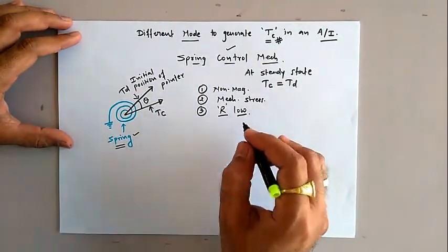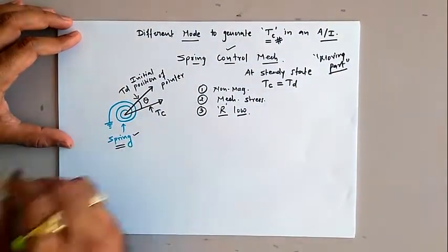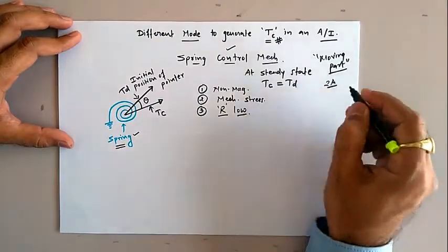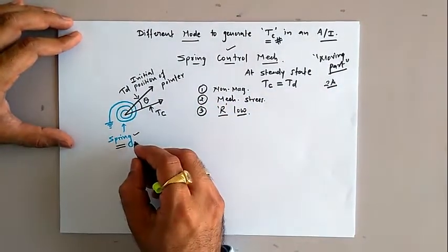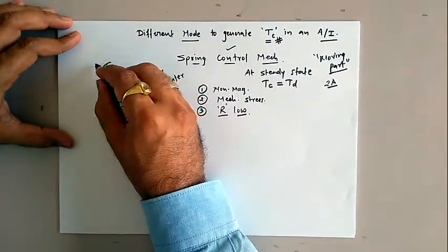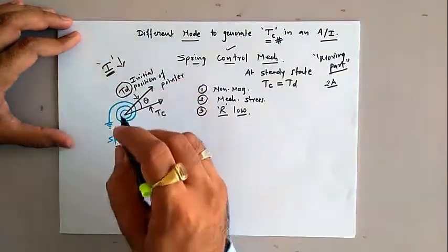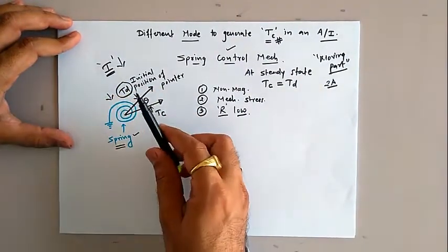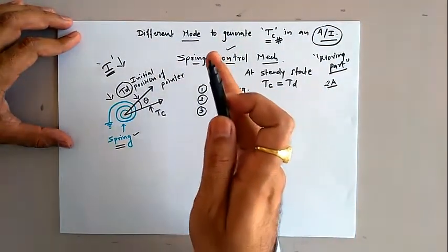The spring must offer very low resistance because analog instruments are designed such that whatever current flows through the moving part also flows through the corresponding spring. For example, in a PMMC type instrument, if the moving coil carries 2 amperes, the same 2 amperes flows through the spring. Since the deflection torque is proportional to the input current, if you select a spring with very high resistance, it will reduce the input current magnitude, thereby reducing the deflection torque. This means the pointer will not indicate the exact value of the unknown quantity — the instrument will read less than the actual value.